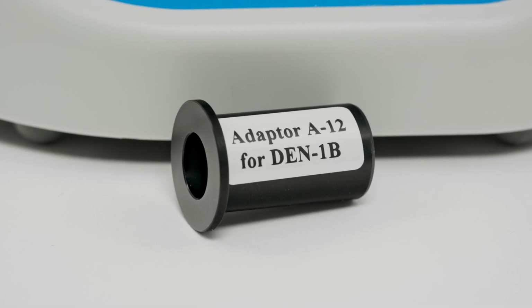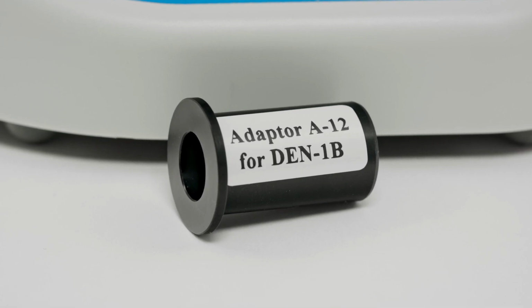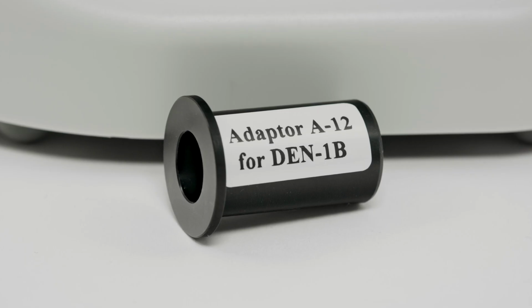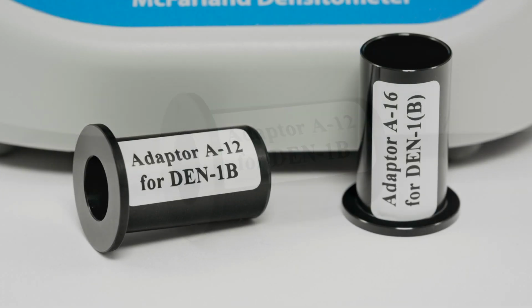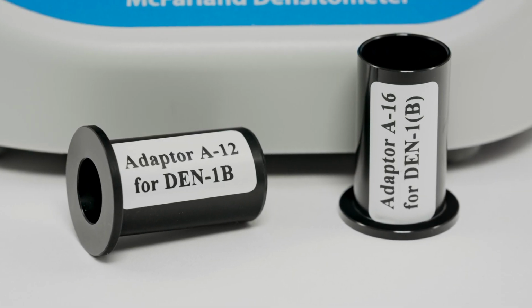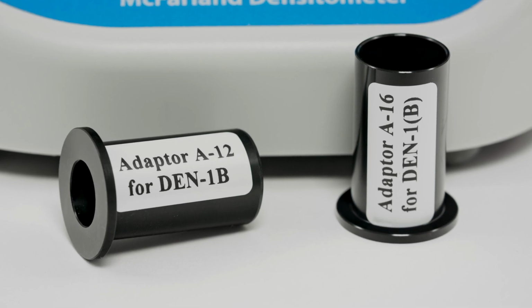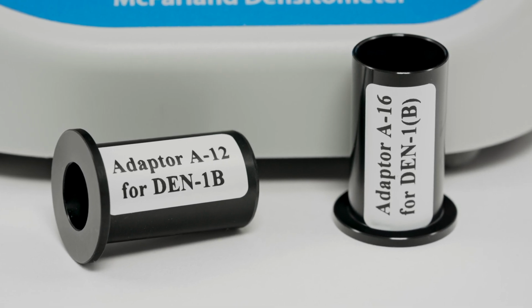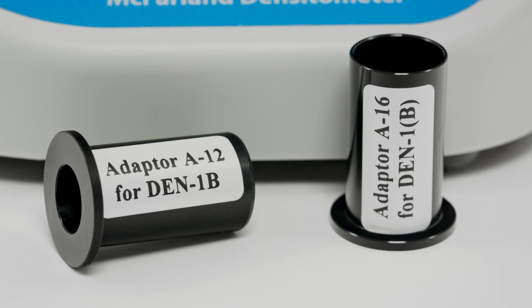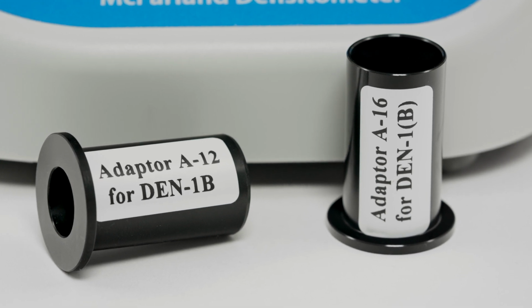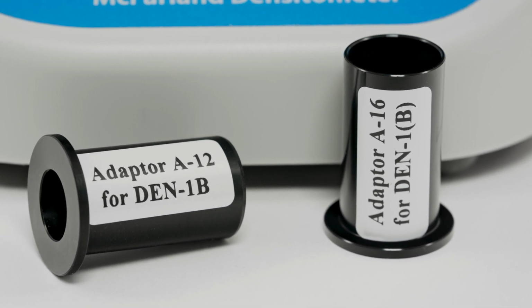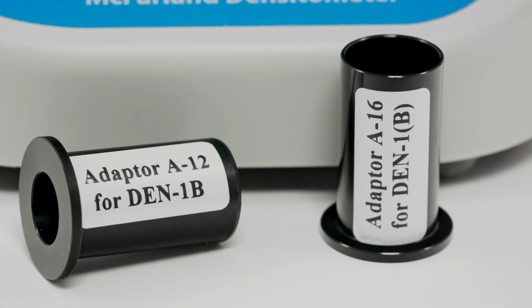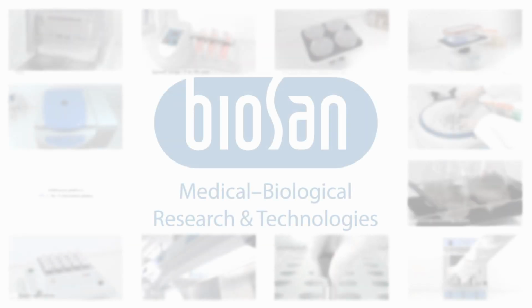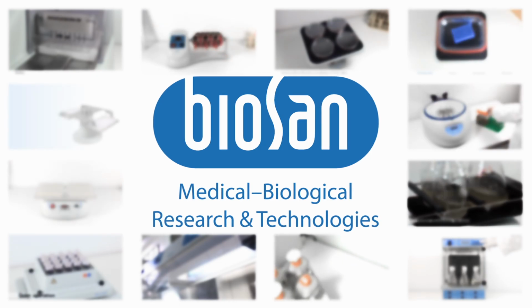Use of different size McFarland calibration kit, for example 12 mm standards, will require an optional A12 adapter. 18 mm McFarland calibration kit can be used by removing the included A16 adapter. Also, if you are using standards from other manufacturers, it is important that they do not fit loosely in the socket. For more information, contact your regional Biosan representative.